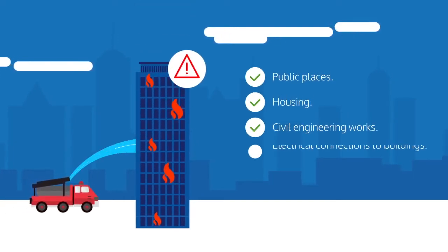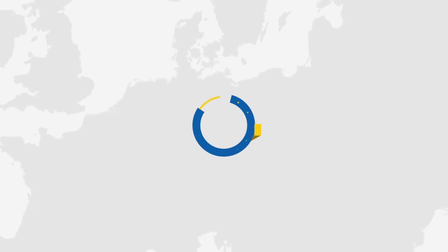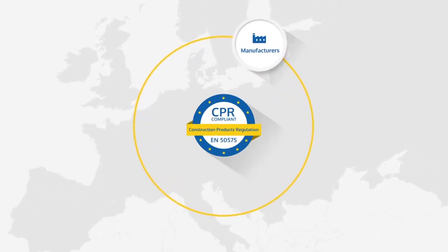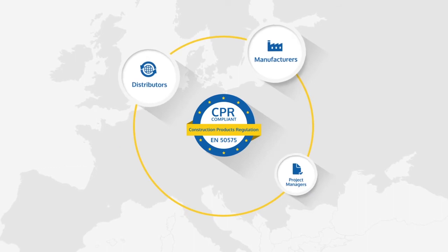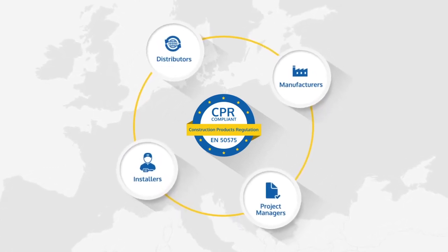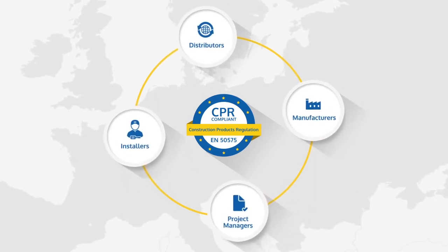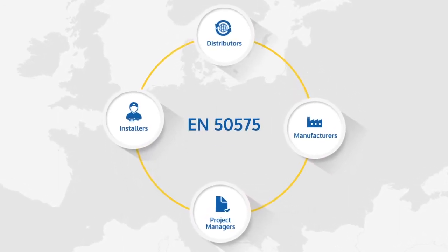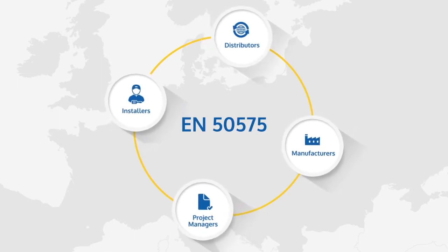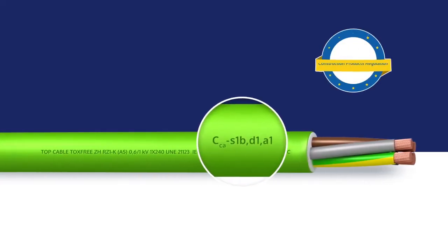The CPR applies to all products intended to be used permanently in construction: public places, housing, civil engineering works, electrical connections to buildings, external lighting, etc. The implementation of the new CPR safety requirements obliges manufacturers, distributors, project managers, and installers in the European Union to manufacture, distribute, prescribe, and install cables that comply with the harmonized standard EN 50575.